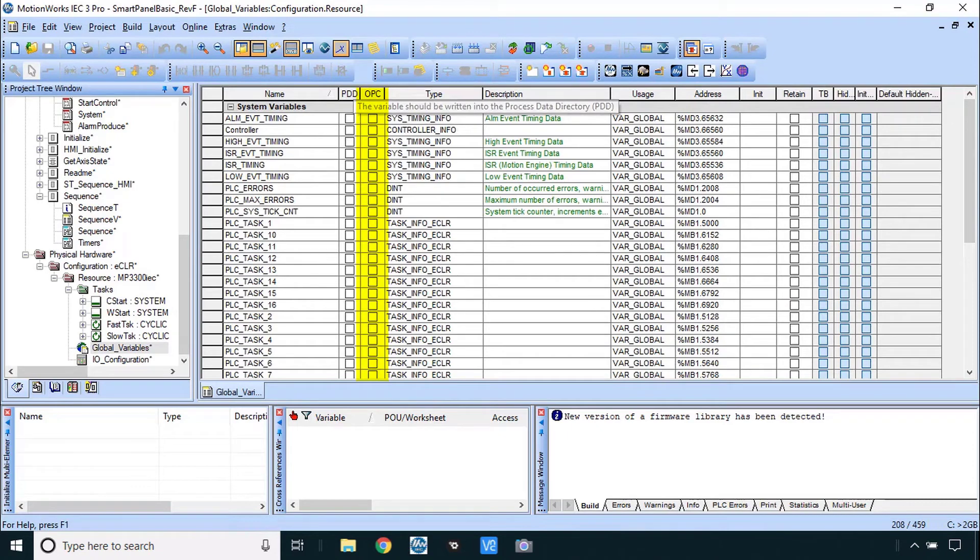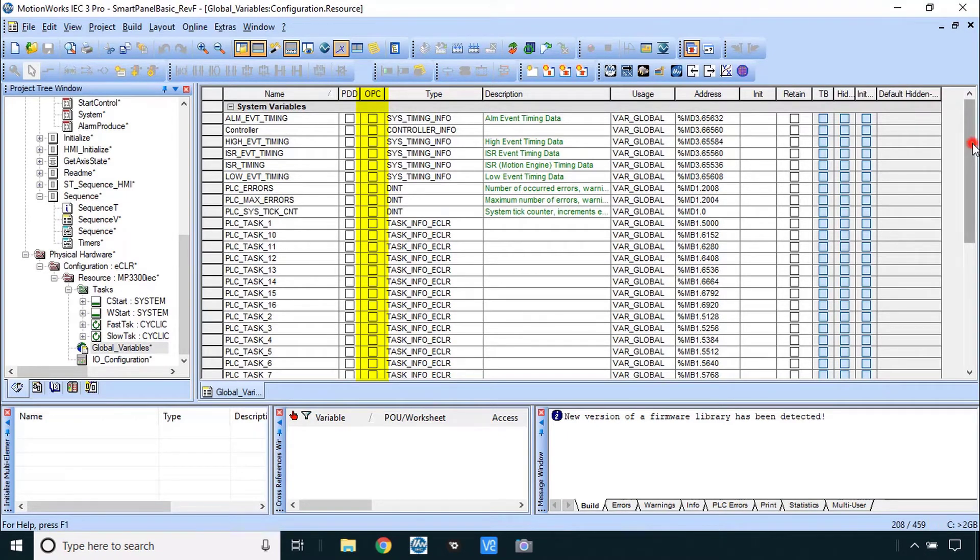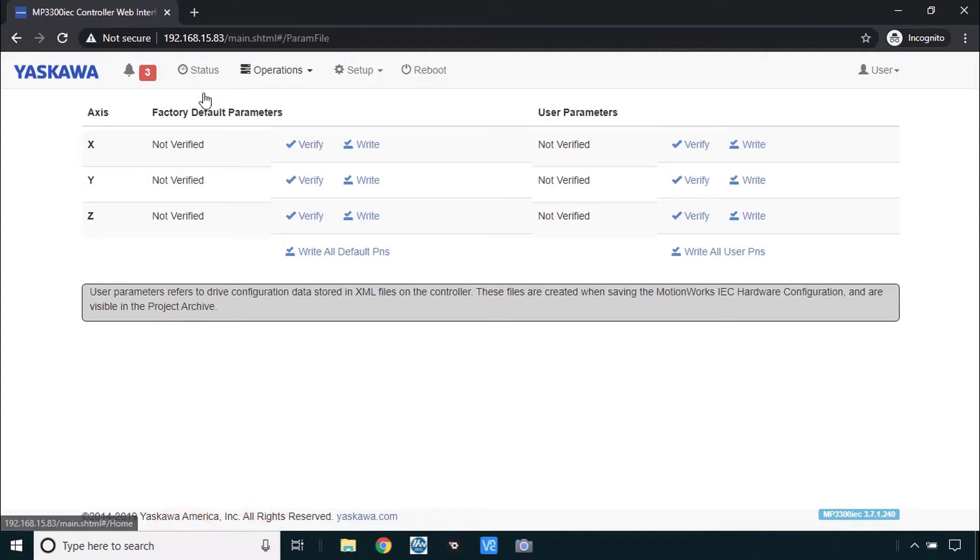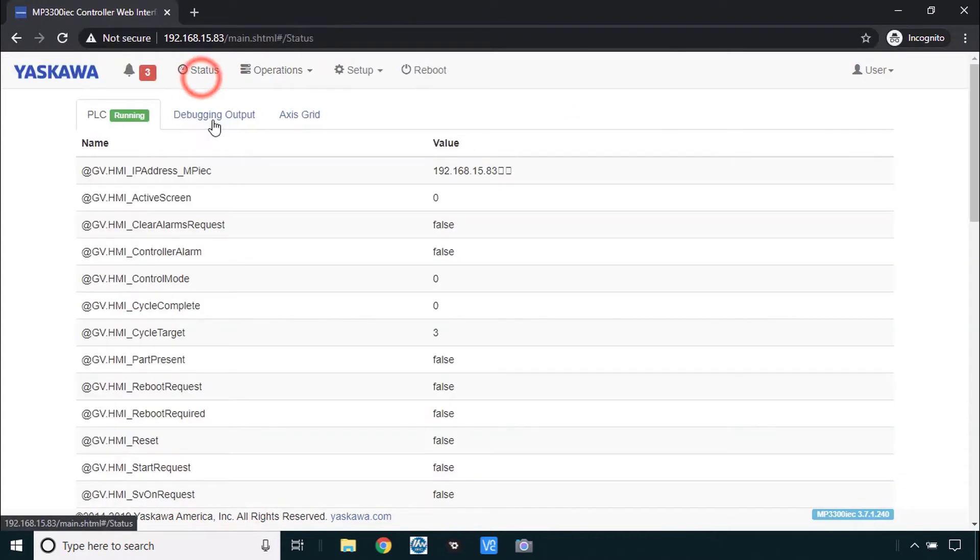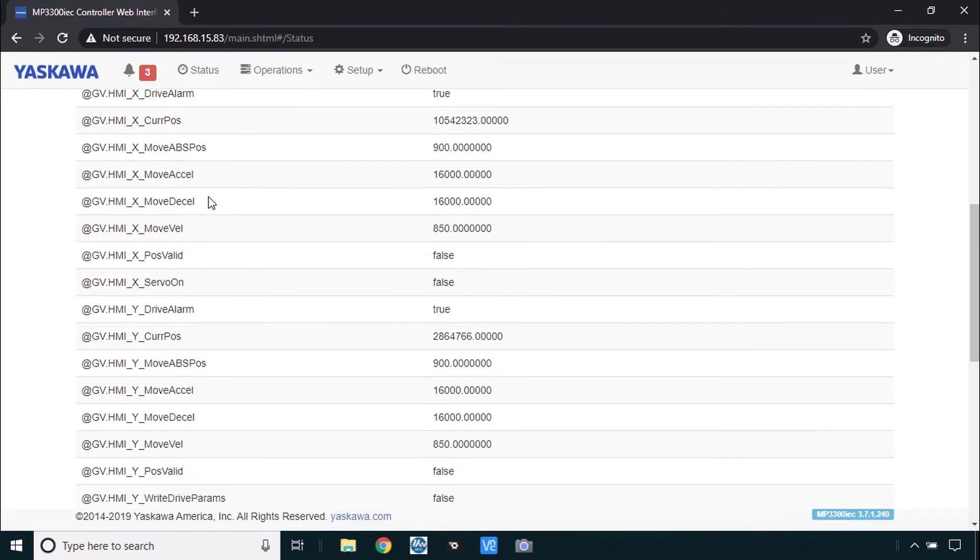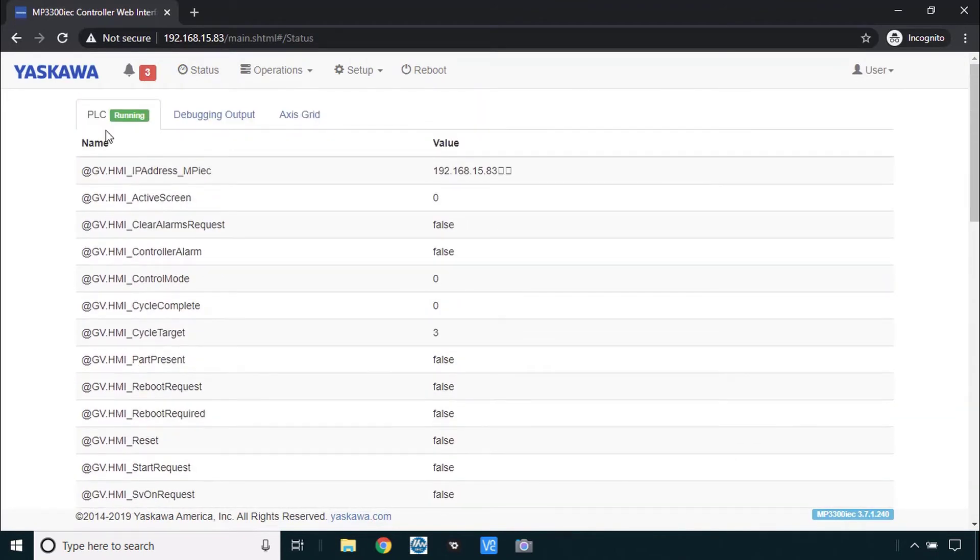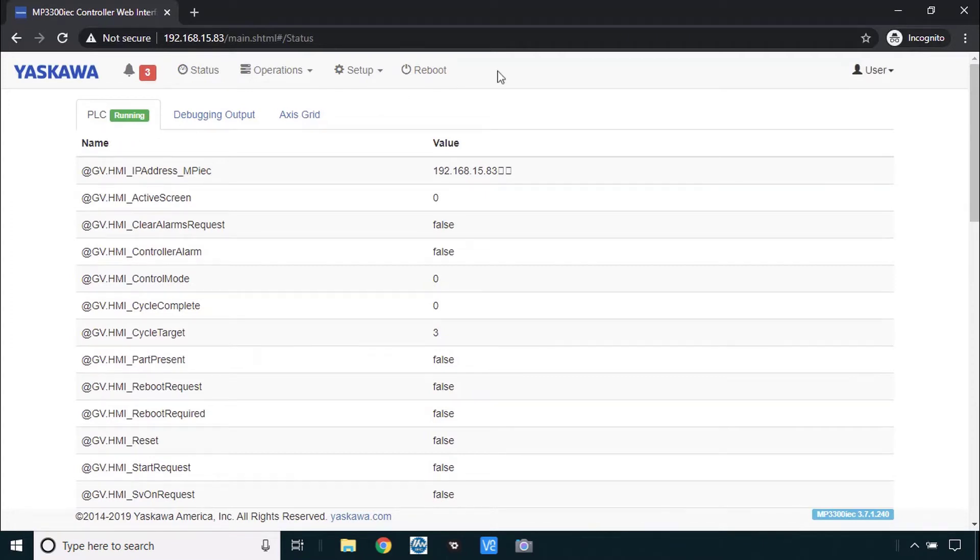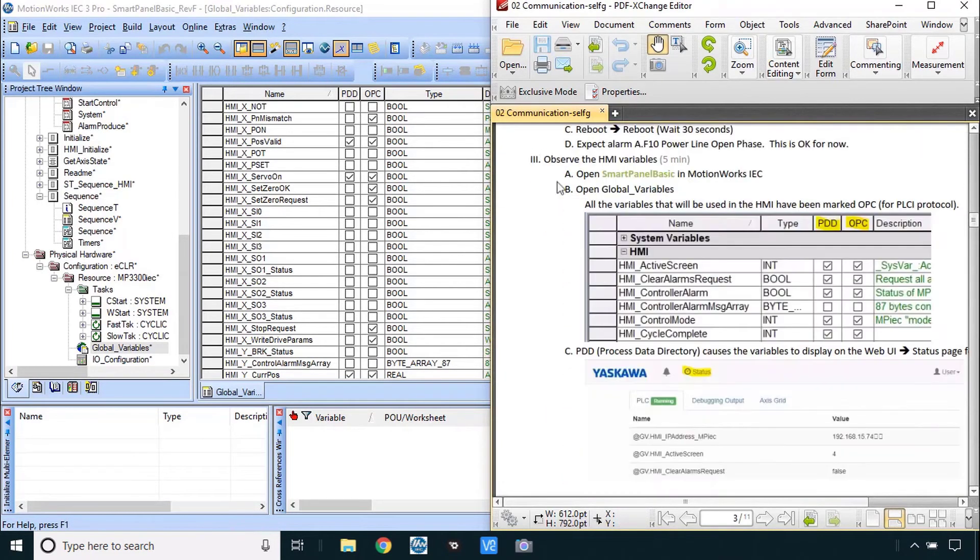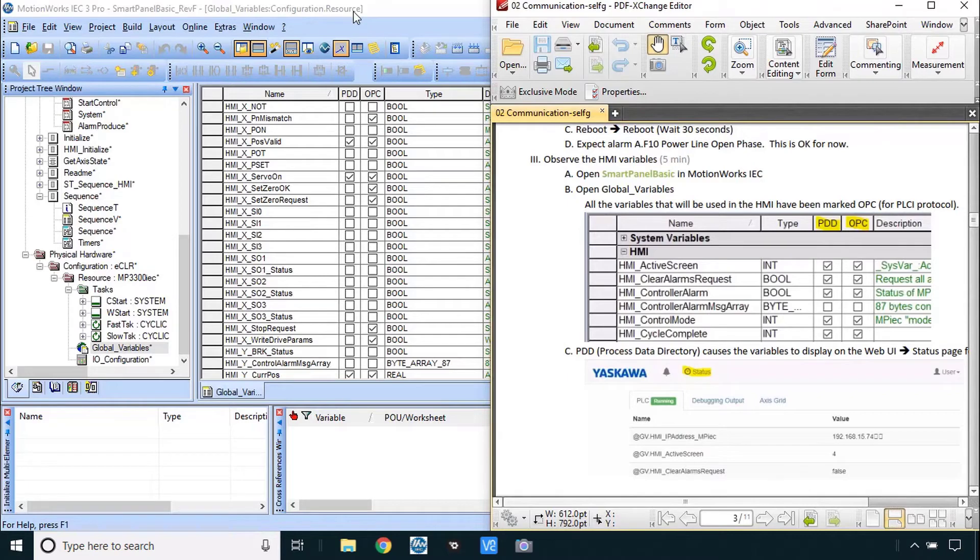And on this project I've put OPC column here rearranged it a little bit and you can see that some of these are marked OPC by the way others are marked PDD. And what that means is they will appear in the status of the web UI here. And this can help if you need some troubleshooting, just open the web UI come to status, might be a little easier than using MotionWorks IEC if you're not familiar with it. That's what step C was about here, PDD or process data directory. Now we technically don't have to make or download this project. This project is only for reference and later to make the boot file. So let's just move on here to Movicon.